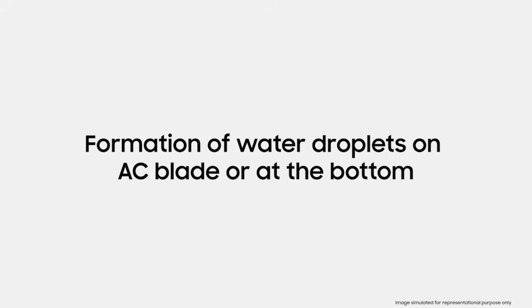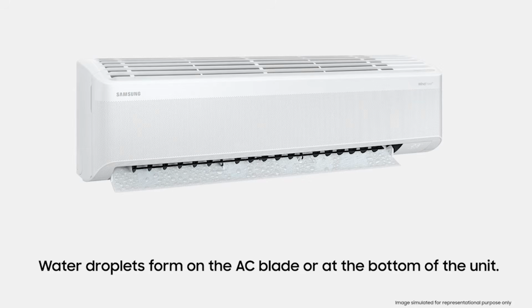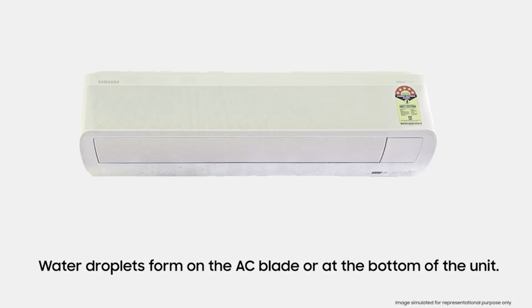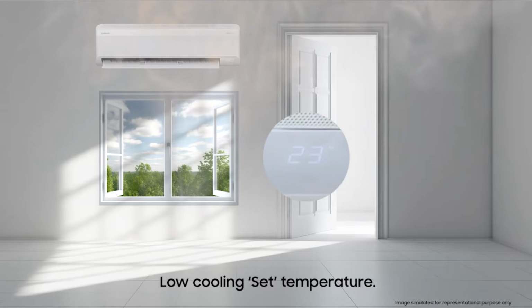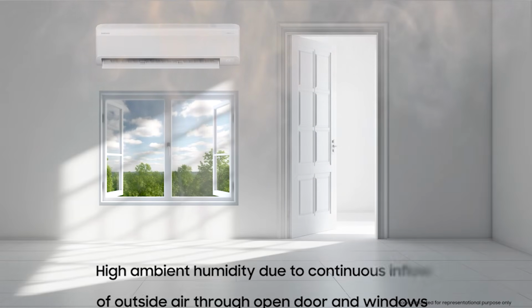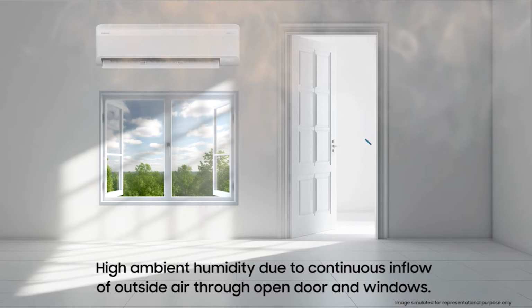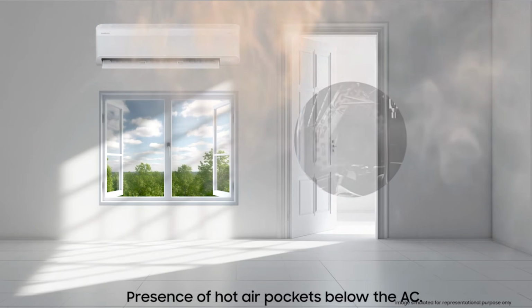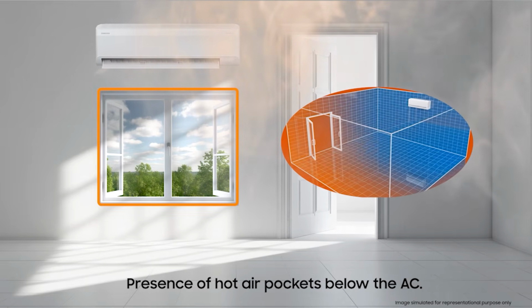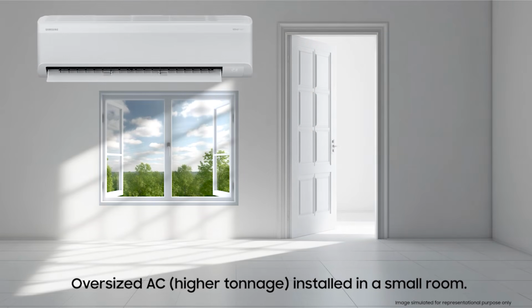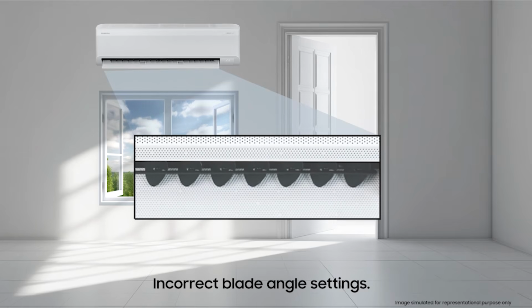Formation of water droplets on the AC blade or at the bottom. Water droplets form on the AC blade or at the bottom of the unit. The possible causes are low cooling set temperature, high ambient humidity due to continuous inflow of outside air through open doors and windows, low indoor fan speed, presence of hot air pockets below the AC, oversized AC installed in a small room, and incorrect blade angle settings.